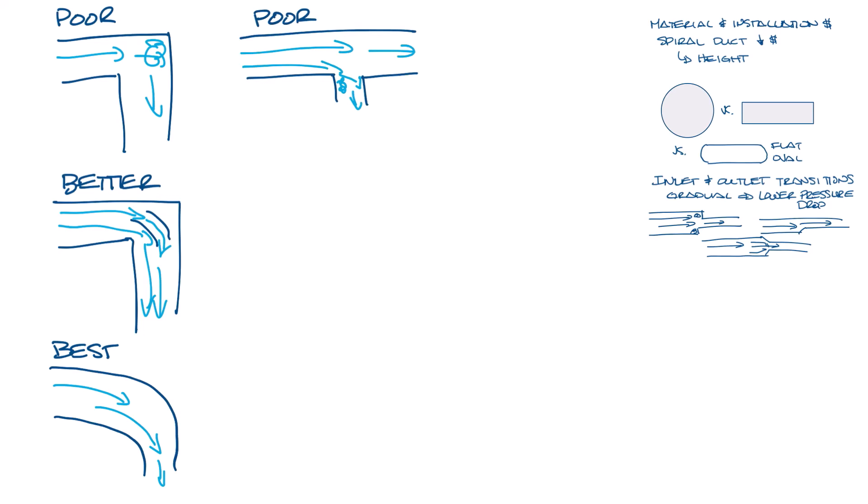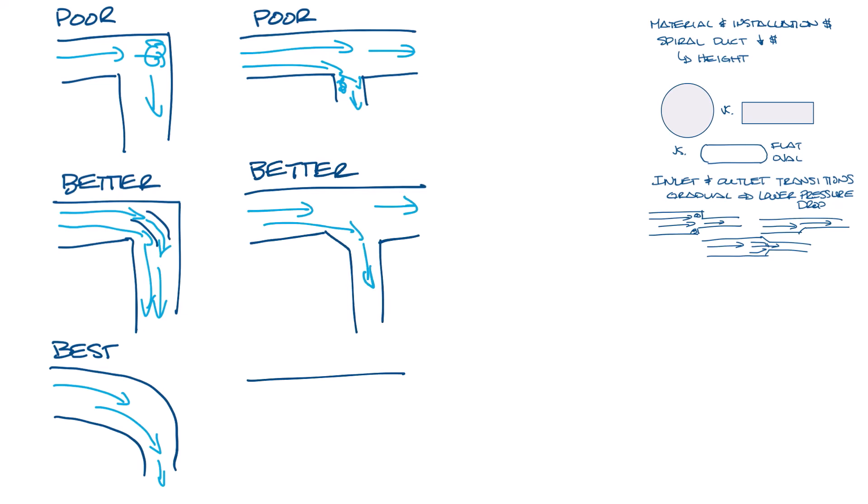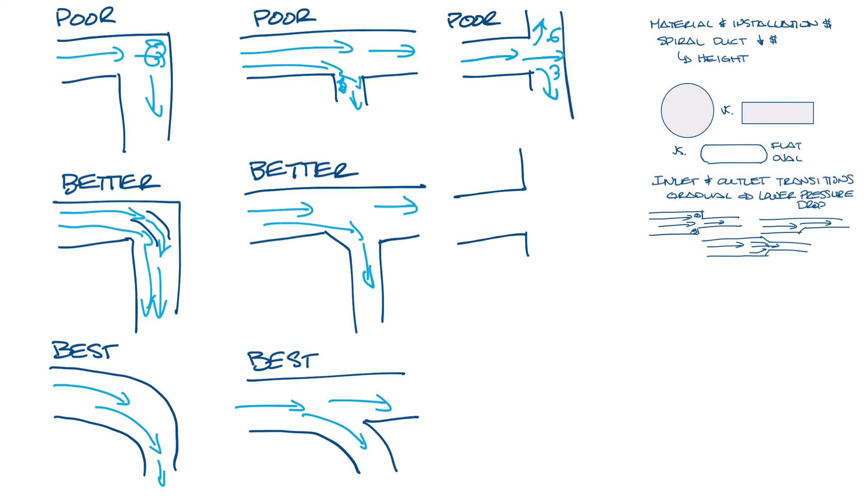And here's another example of a poor, better, and best option. Same thing would happen if you have tees in the ductwork. So making your tees softer or using turning vanes would help here too.